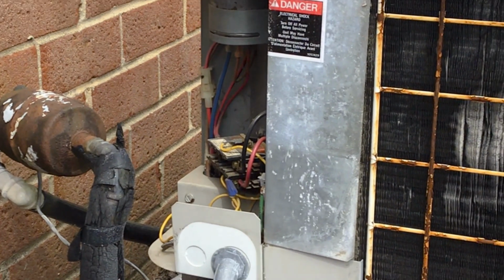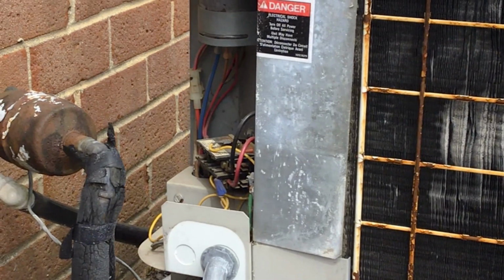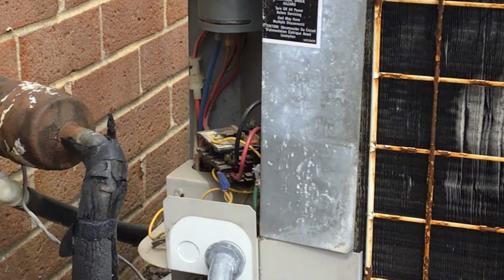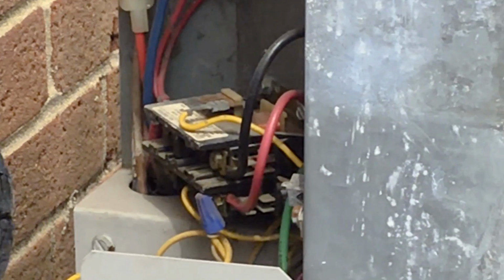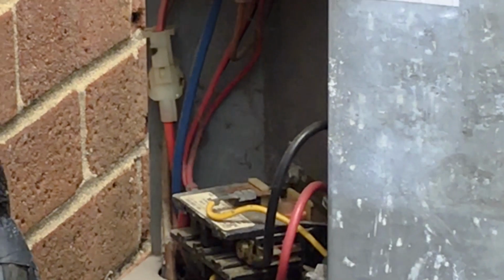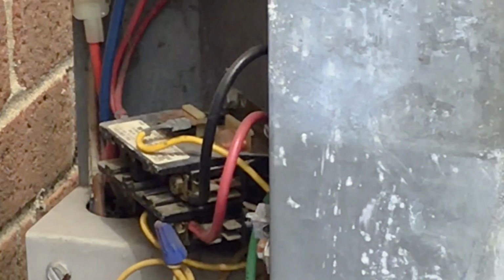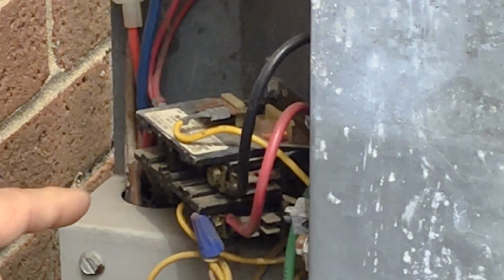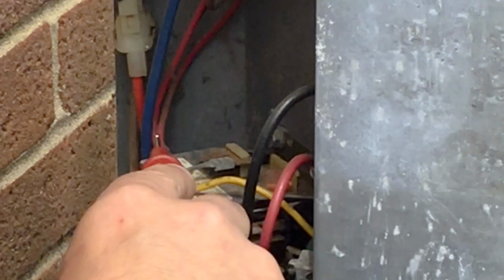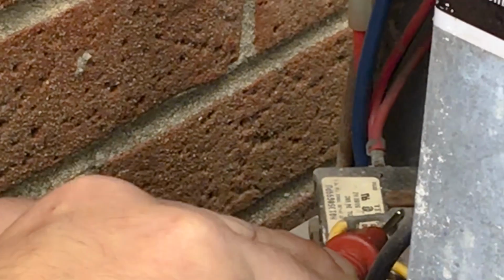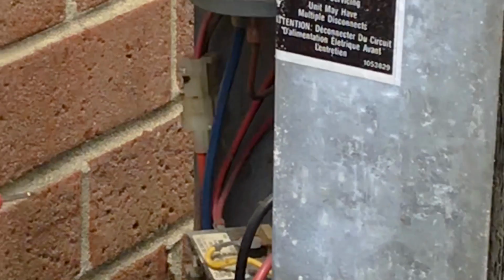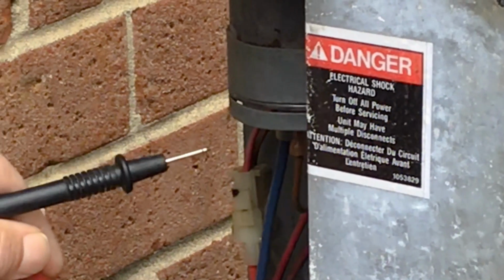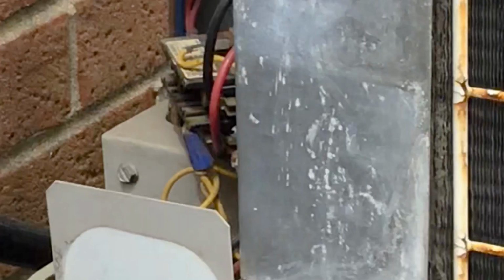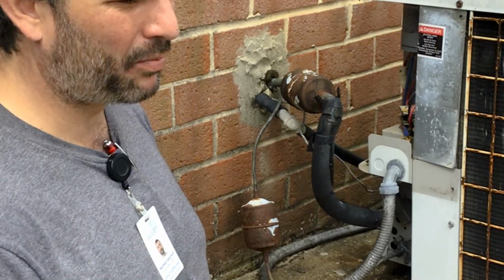On the other side, I did leave the breaker on for the furnace. One of the quickest inspections you can do to narrow down which voltage your problem is on, and we're going to start by talking about the 240 volt components, is sometimes it's visual. You can see if that contactor, your AC contactor, is closed, and then you can also check the voltage on the side terminals. Look at the meter. You should get 24 volts. So anytime your contactor is closed, you have your 24 volts across your contactor to your low voltage terminals, and nothing is operating inside this unit, you know quickly that you have a 240 volt problem.